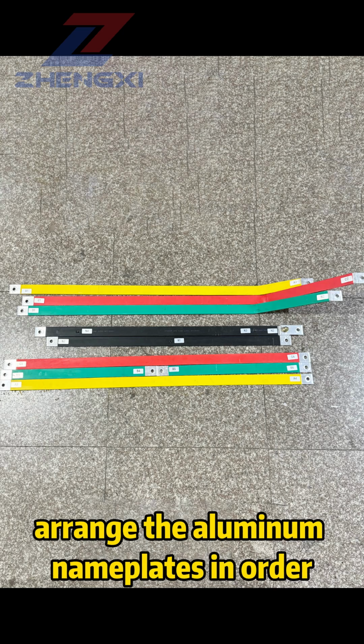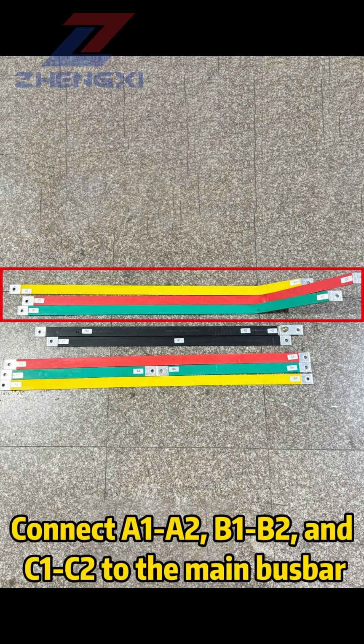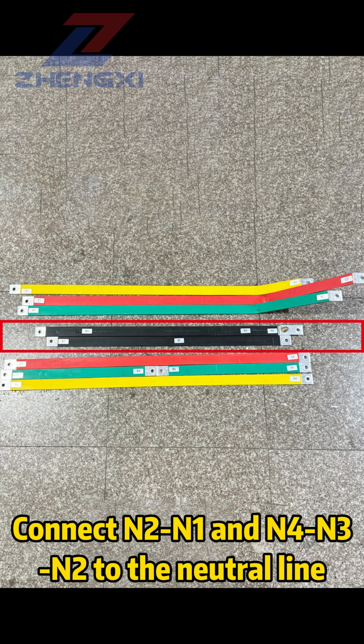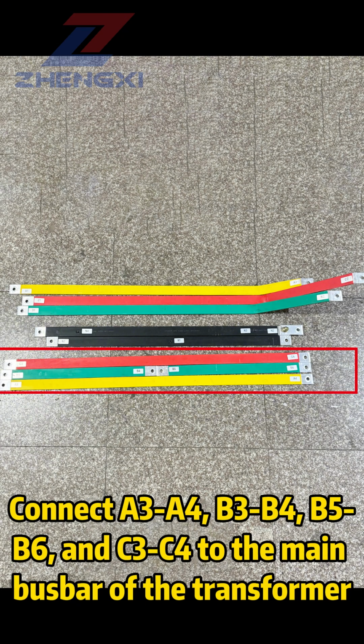3-phase high-power split regulation voltage stabilizer assembly video. Arrange the aluminum nameplates in order. Connect A1, A2, B1, B2, and C1, C2 to the main busbar. Connect N2, N1, and N4, N3, N2 to the neutral line.